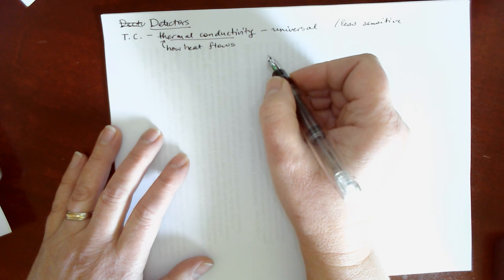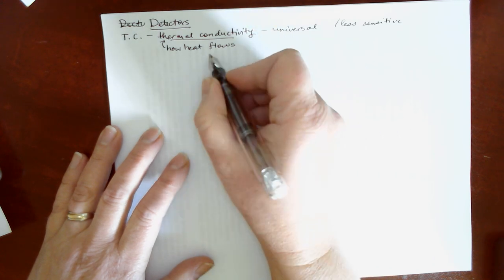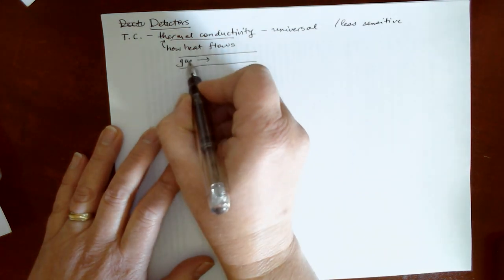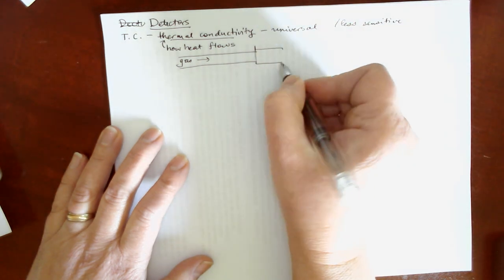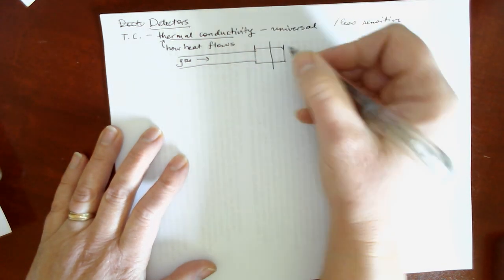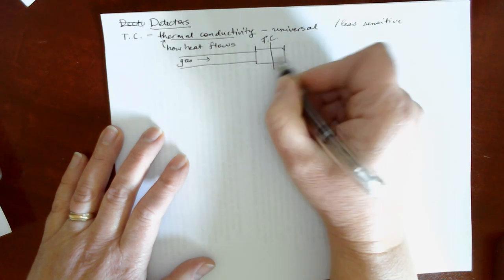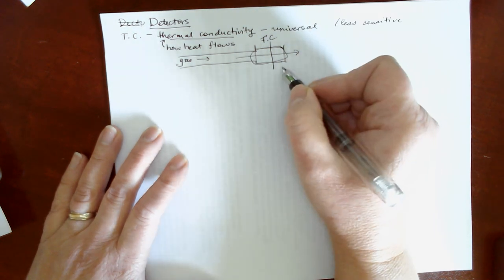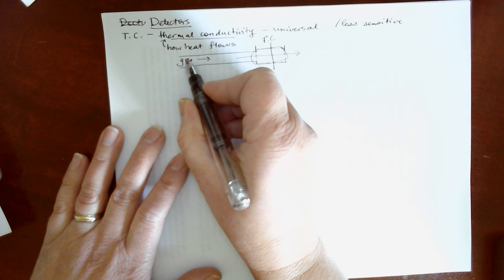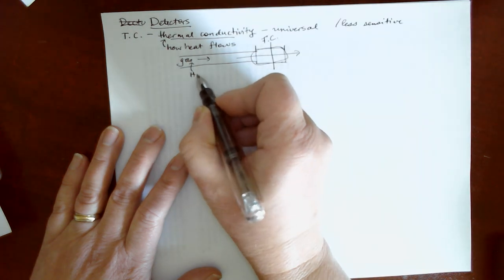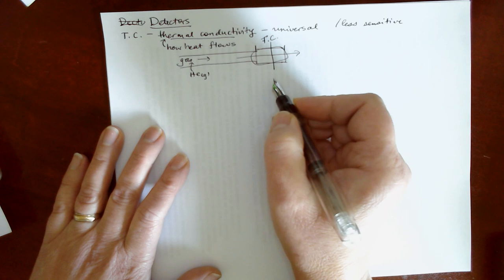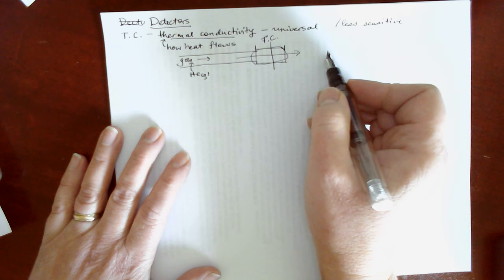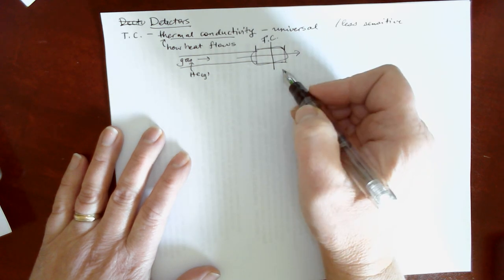So what we're looking at in the detector area, there is, of course, the carrier gas flowing through this. And so if you have your detector right here, then you can measure your thermal conductivity across this area of your detector. And as the gas goes through, the thermal conductivity would stay constant if the gas is just one item. So for example, if you're using helium gas for your carrier gas, or argon or nitrogen, whatever you have, then as long as that gas stays consistent, the thermal conductivity is going to stay consistent also.